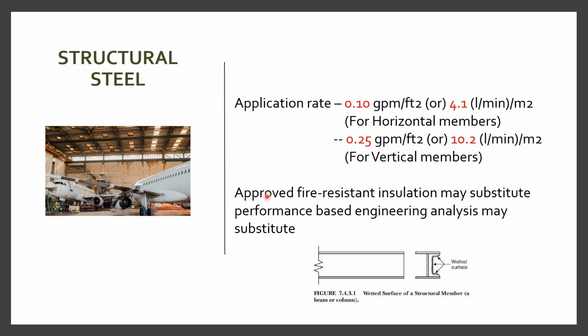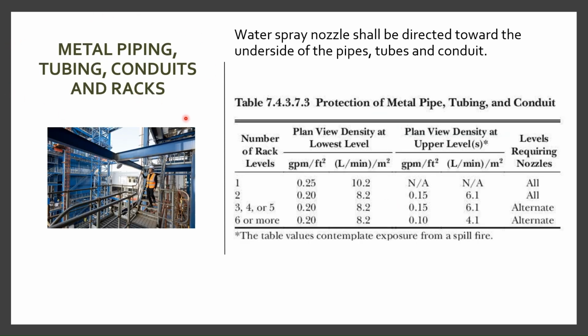So one more point to be discussed here: approved fire resistant insulation may substitute performance based engineering analysis, may substitute the water spray system. So it means the water spray system can be avoided if it is protected with approved fire resistant insulation. So here we are going to discuss metal piping, tubing, conduits and racks. In power plants and in most industrial projects, if you are aware, we need to protect these particular items as well through water spray nozzles.